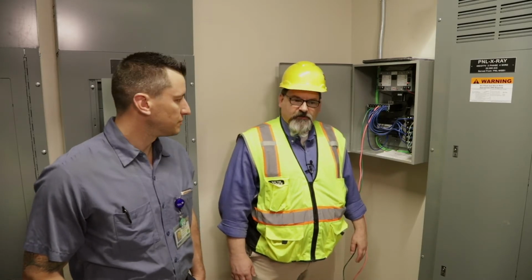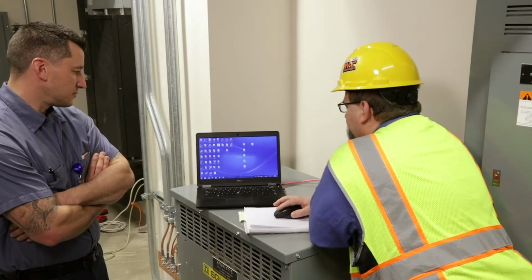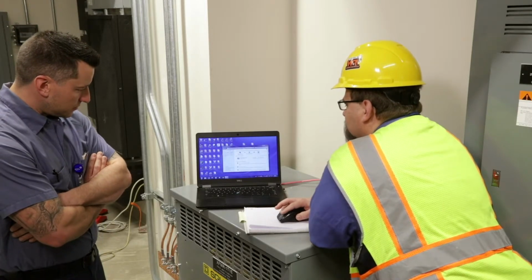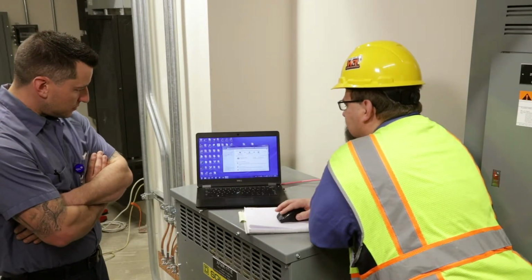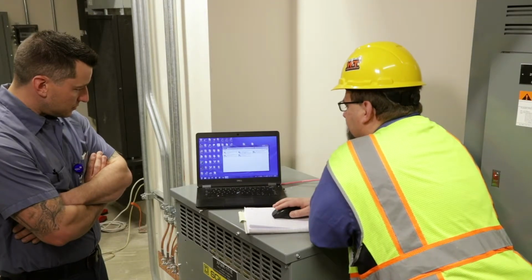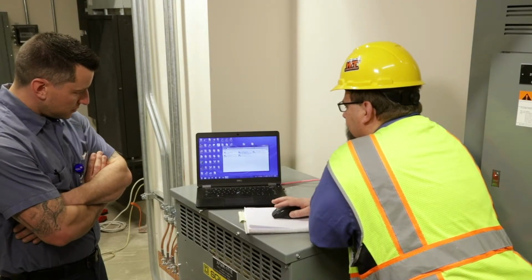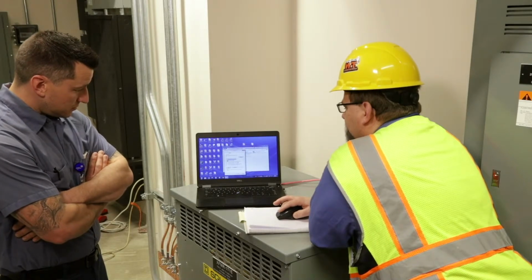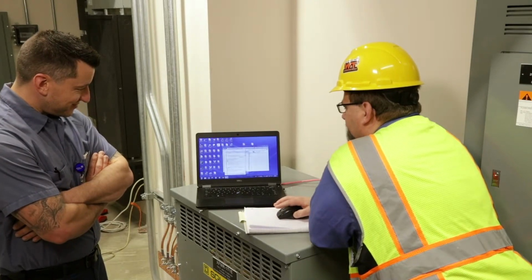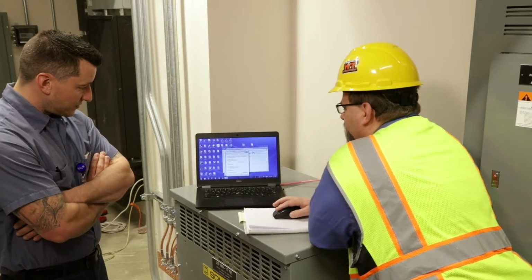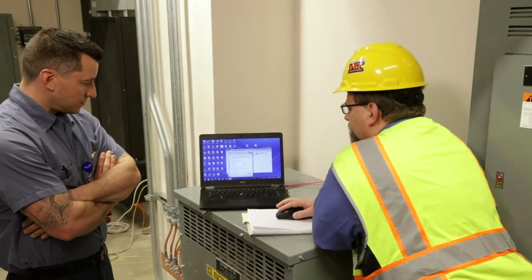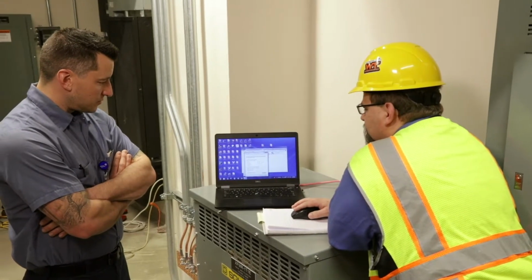Okay. So the interface is a network interface. We're going to edit our computer's interface. This is what you would do when you bring your notebook, essentially, right? Here's the connection that we have, a local area connection. We look at the properties. We're going to just keep it simple and talk TCP IPv4. These 3 numbers have to match between your computer and your direct interface to our device. And you're just going to plug directly from your computer to that switch over there that we showed you.